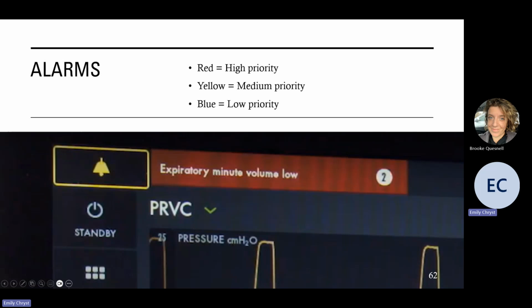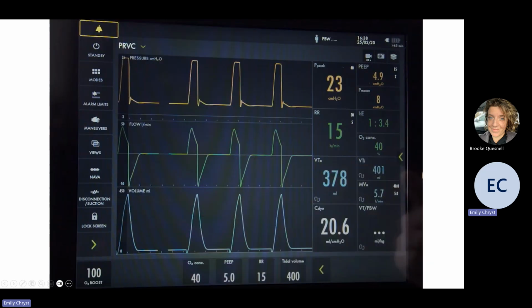I'm not going to talk about what the alarms are and how to troubleshoot them because your ventilator will do it for you. You have an alarm, you click on this, it's going to open up a screen and it's going to tell you what that alarm is, why it's happening, and what you can do to fix it. Additionally, back on that settings screen, whatever parameter is causing the alarm is going to blink at you. Make it really, really, really easy.